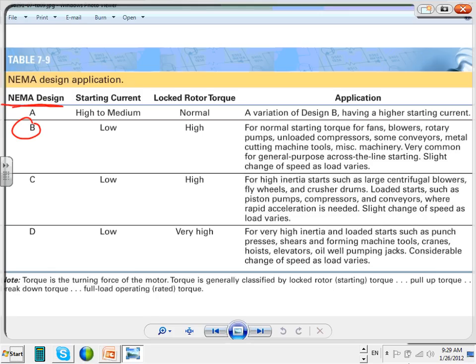NEMA sizes. So Nick, you're going to hear about NEMA size for motors, the sizing based on NEMA. NEMA B is what you're going to remember, almost. NEMA B is good for all this stuff here: normal start torque for fans, blowers, rotary pumps, unloaded compressors, conveyors, and all these machines, very common, general purpose. You are almost defaulted to design B. What does that mean? When they design the guts of the motor, guys, they design it different. There are 4 designs. The higher the design, the more expensive. The D is a very expensive motor to buy, a design D motor.